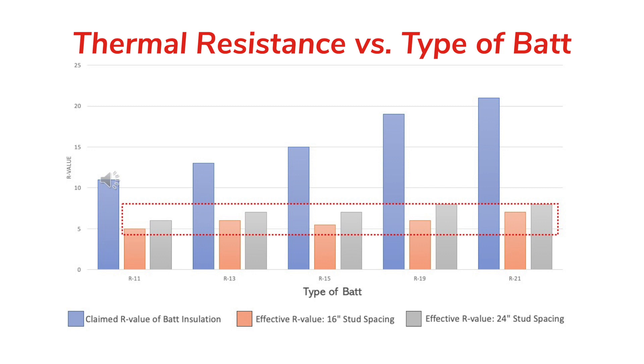As illustrated here, part of the reason why increasing the amount of insulation only within the cavity is not an efficient way to increase the effective R-value of the assembly is because of the effects of thermal bridging. Even when up to R-21 batt insulation is used, because the insulation has solely been placed in between the conductive steel studs, there is no significant increase in the actual R-value of the assembly, as shown.